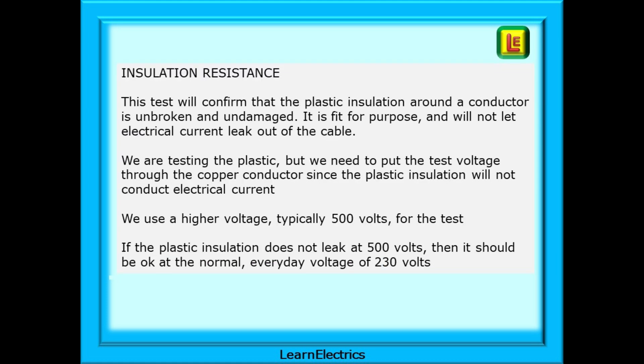The insulation resistance test is different. It will confirm that the plastic insulation around the conductor is unbroken and undamaged, and that it is fit for purpose and will not let electrical current leak out of the cable. We are testing the plastic, but we need to put the test voltage through the copper conductor since the plastic insulation will not conduct the electrical test current.